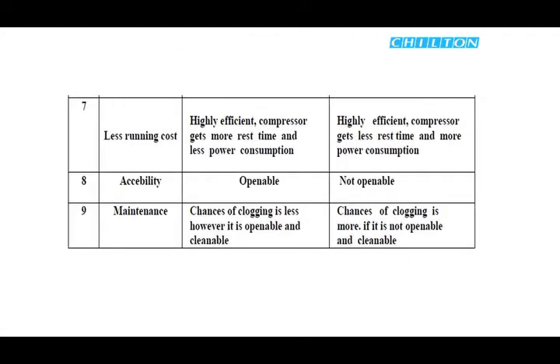Less running cost, Chilton: highly efficient. The compressor gets more rest time, hence less power consumption. Competitor: the compressor gets less rest time, hence more power consumption. Accessibility, Chilton: openable. Competitor: not openable. Maintenance, Chilton: chances of clogging are less because it is openable and cleanable. Competitor: chances of clogging are more because it is not openable and cleanable.